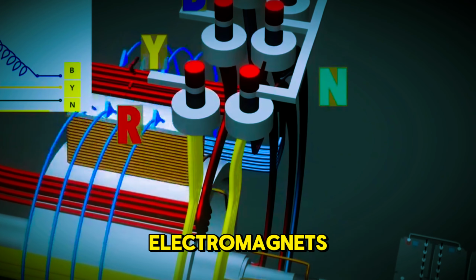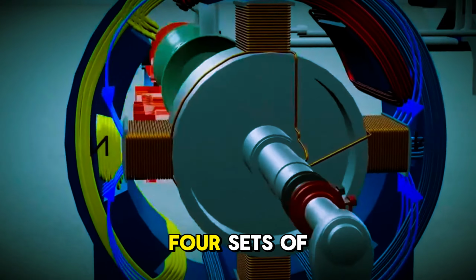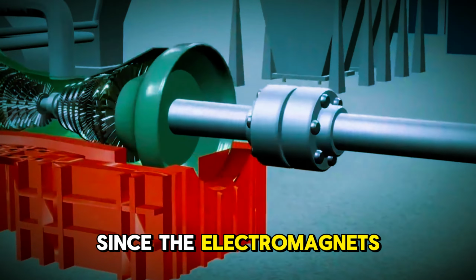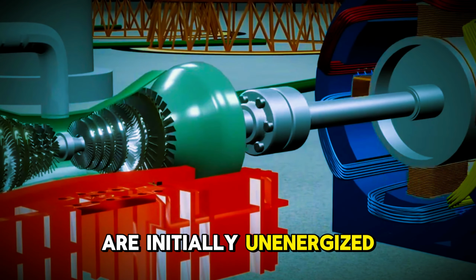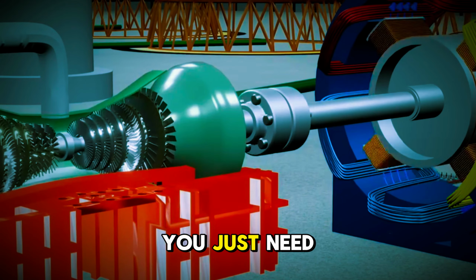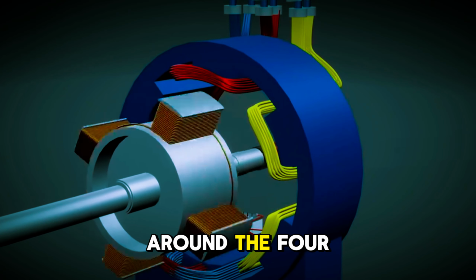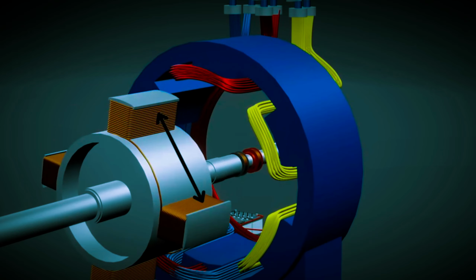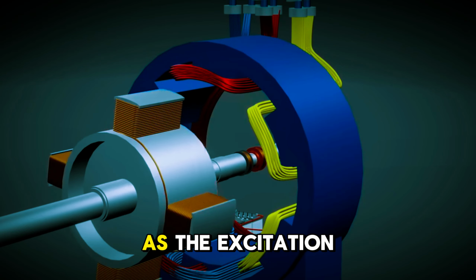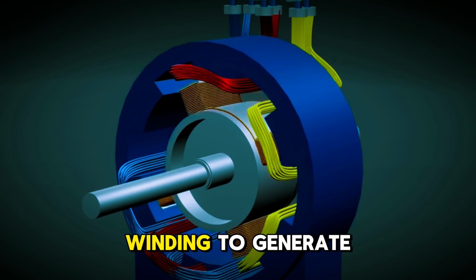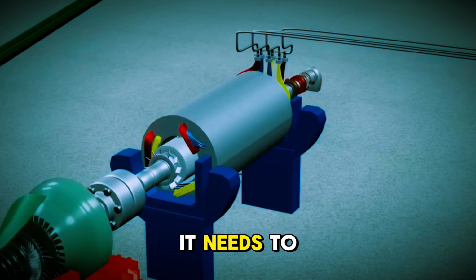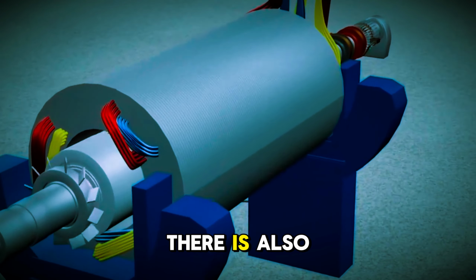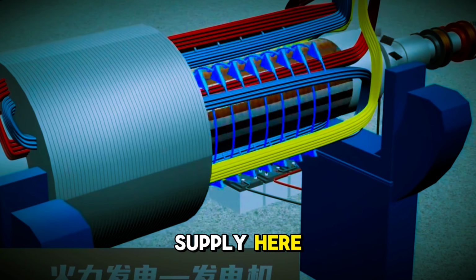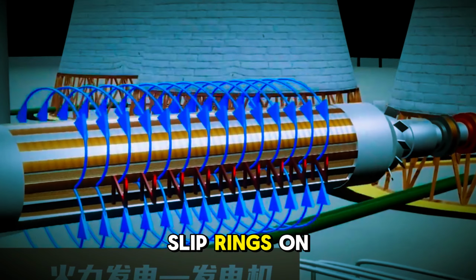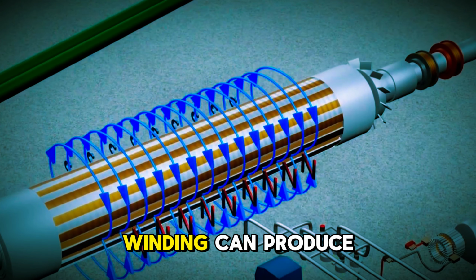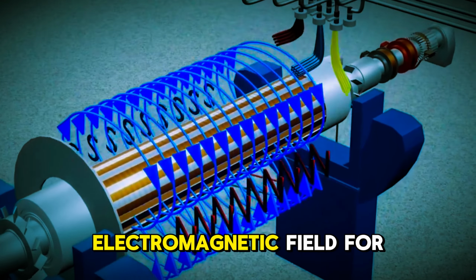Generators actually use electromagnets. It consists of 4 sets of coils. Since the electromagnets are initially unenergized, installation is very convenient. You just need to wrap the 4 sets of coils around the 4 protruding magnetic poles. This coil combination is also known as the excitation winding. For the winding to generate a magnetic field, it needs to be energized. Therefore, there is also a DC power supply here, connected by 2 wires to the 2 slip rings on the rotor. This way, the winding can produce a very stable electromagnetic field.